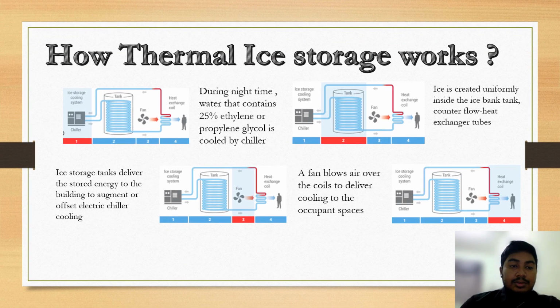So this is how the thermal ice storage works. As we can see, during night time, water that contains 25% ethylene or propylene glycol is cooled by the chiller. So the next, second step, ice is created uniformly inside the ice bank tank, counterflow heat exchanger tubes. For the third step, ice storage tanks deliver the stored energy to a building to augment or offset electric chiller cooling. So the last step, a fan blows air over the coils to deliver cooling to the occupant space.